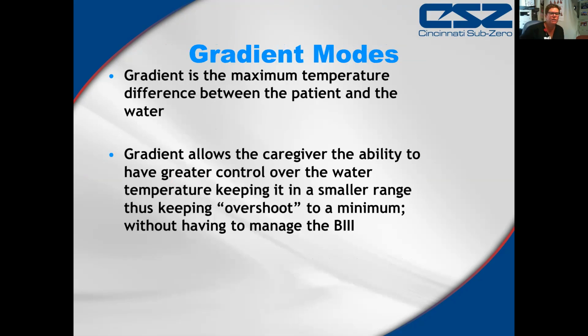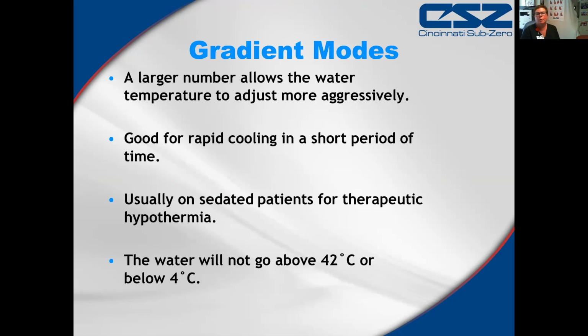So once we have achieved target temperature, then we will move to a gradient mode. And so there are 2 gradient modes that we can use. But the reason why we switch to the gradient mode is it allows the caregiver much more control over the water temperature so that there is not a huge swing in the patient's temperature. So it minimizes overshoot. So gradient modes, a larger number allows the water temperature to adjust more aggressively. And that more aggressive is what we saw in the automatic mode.